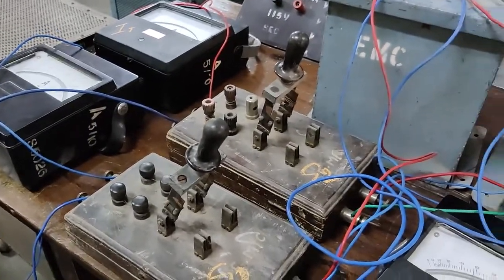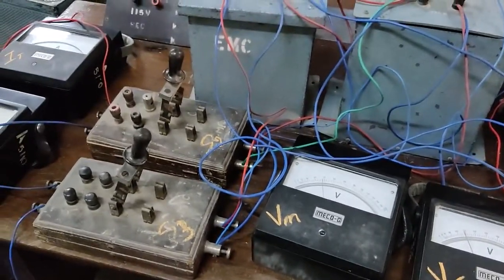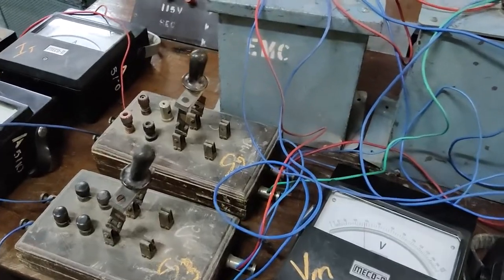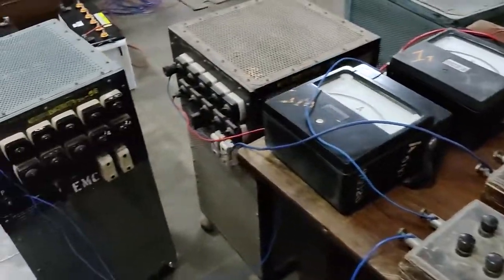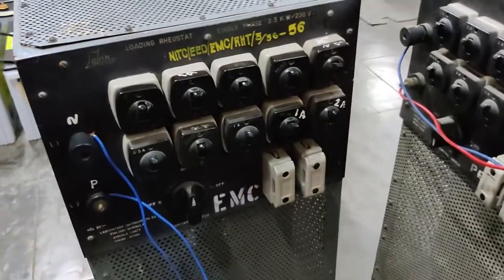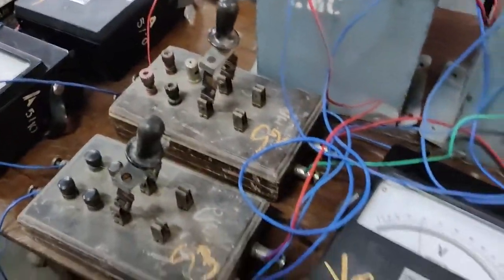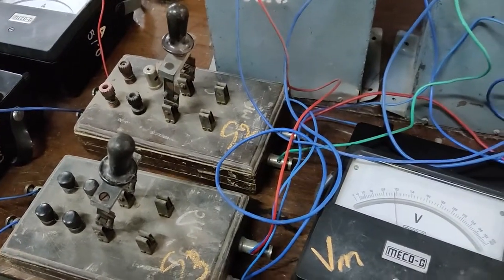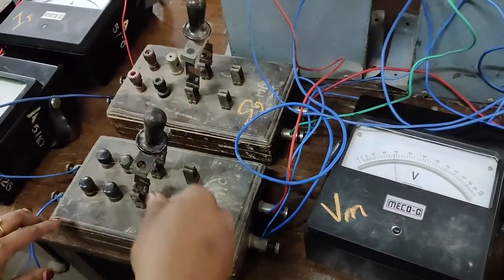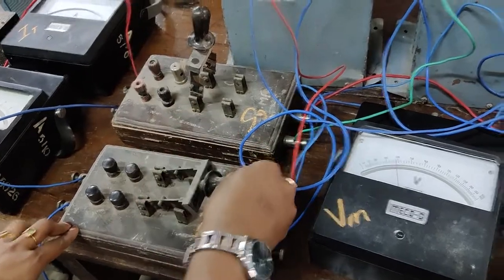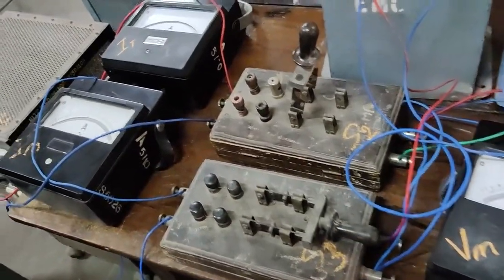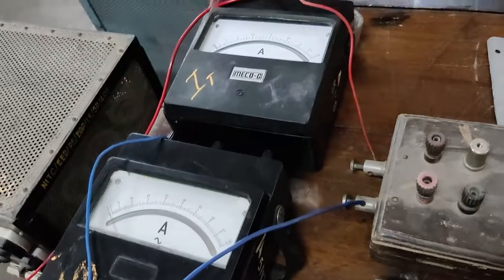After taking the no load readings, let's load our main transformer first, so that our loads are in safe condition, that is no load position, and we are closing the switch S3, that is connecting the main transformer to the loading rheostat. Let's close switch S3 first. So now the condition is S3 closed and switch S2 open, so that we are loading the main transformer only using the loading rheostat.